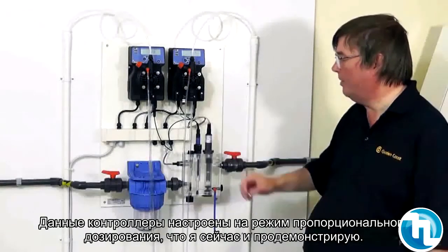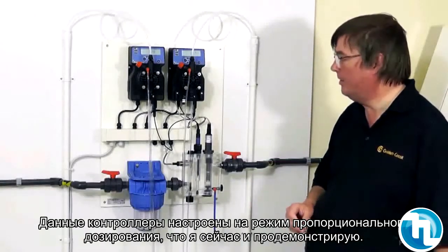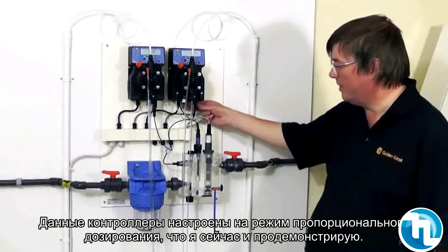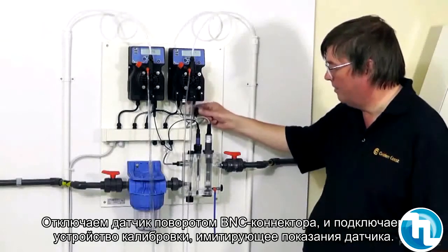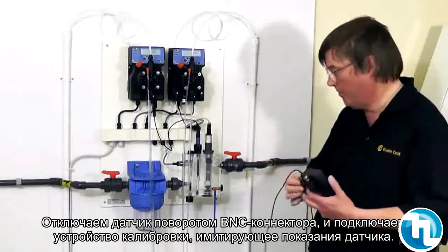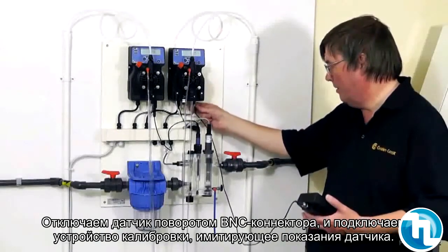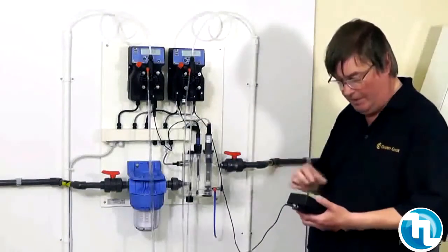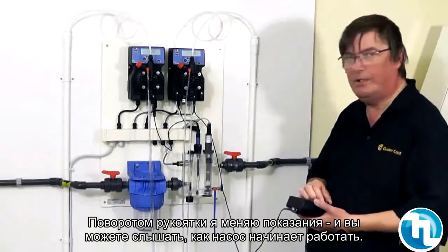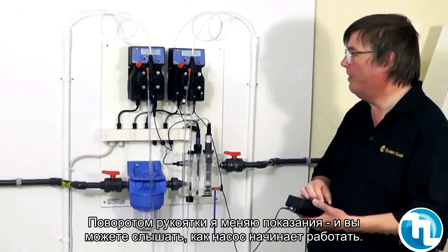This particular controller is set up for proportional dosing, which I'll show you now by disconnecting the probe. It's a 1/4 turn BNC plug, and we'll connect on our calibration meter, and I'll now turn the reading down and you'll hear the pump speed up the further we get away from the set point.